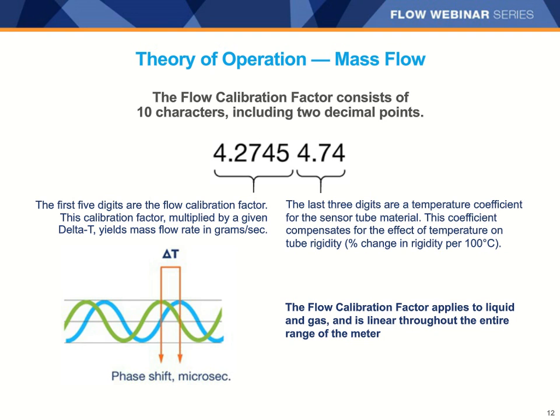The last 3 digits of the calibration number are a temperature coefficient for the sensor tube material. This coefficient compensates for the effect of temperature on tube rigidity, or Young's modulus of elasticity, in percent change in rigidity per 100 degrees C. The 4.74 number shown is for a stainless steel meter. A different number would be used for other metallurgies like Hastelloy C or titanium. The RTD that measures the tube temperature is plus or minus 1 degree C from the process temperature and can be configured as an output variable.